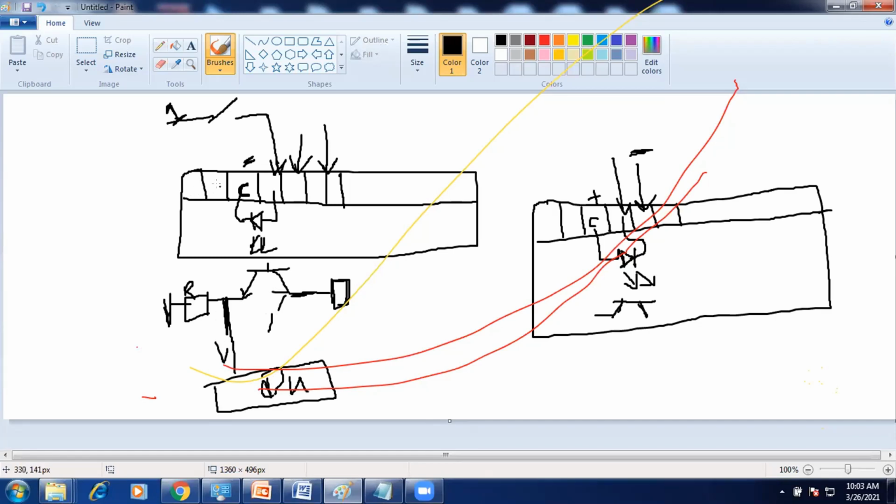The first two positions come under SMPS or without SMPS common. From the fourth position, consider the input parts. Under these input parts we have two types, source input or sink input. Source input means the input side is considered positive, sink input means it is considered negative.